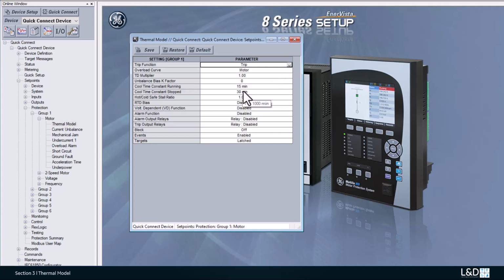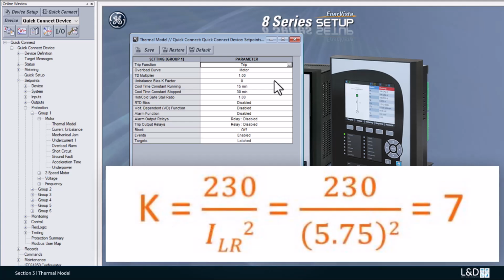For the unbalance bias K factor, we can use this calculation of 230 divided by the locked rotor current squared. So the value is 6.96, so we enter 7 here.